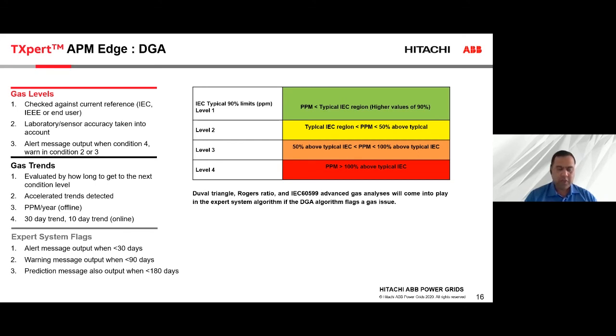And we have also implemented statistical modeling to detect accelerated trends. And we automatically calculate the ppm per year rate of rise. And if it is an online DGA device, we do 30-day short-term trends, and we also do a 10-day very short-term trend. And as soon as we see some issue, our expert system will give you flags. If we see that in less than a month the gas levels are going up, we will straight away send an alert message. If it is within 3 months, we'll warn, and if it is in 6 months' time, we will just give a prediction message.